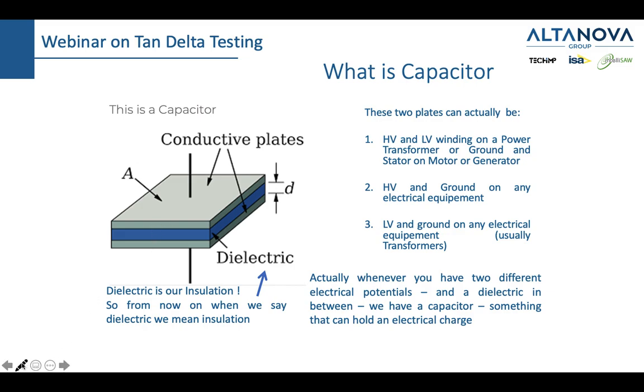It is a physical reality of any transformer, because you can say that this is, for example, a high voltage winding and this is a low voltage winding. In between, you have some paper and some oil, which constitute a dielectric, which in turn, whether we want it or not, constitutes a capacitor. So we could say that we can easily model an insulation as a capacitor.